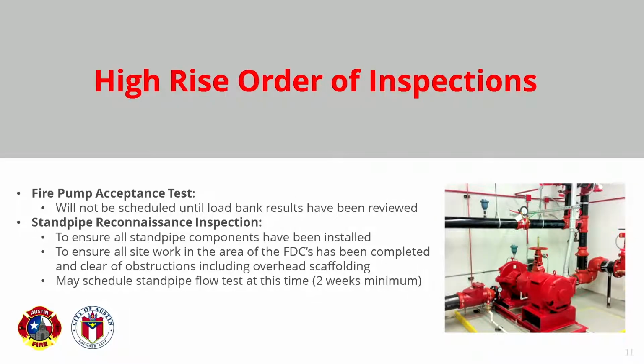Once we have the pump accepted, we can do a standpipe reconnaissance inspection. We look at a lot of things. We're looking at the entire componentry of the standpipes and getting a lot of information that is mostly for us. But the primary thing I'm looking for at a standpipe reconnaissance inspection is, do we have access for our fire engines to be there? Depending on the size of your building, if the requirement for PSI is greater than 225, we're going to have 2 fire engines there. So that's one of the things I'm considering as well.